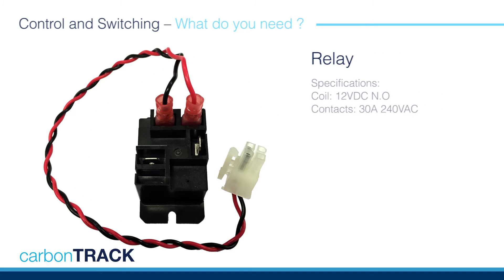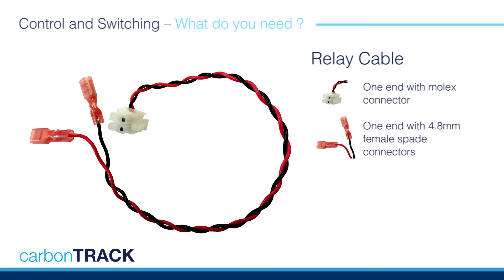The relays you will be using are of the normally open type, rated to switch up to 30 amps at 240 volts AC with a 12 volt DC coil. Each relay connects to the CT100i ports via a twisted pair cable with a Molex connector on one end and female insulated 4.8mm spade connectors on the other.